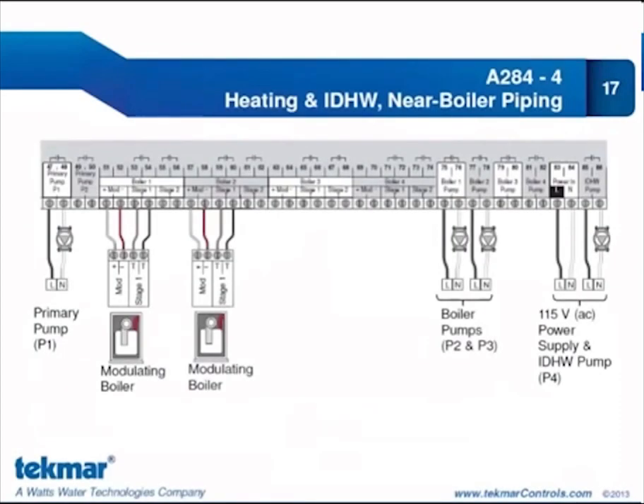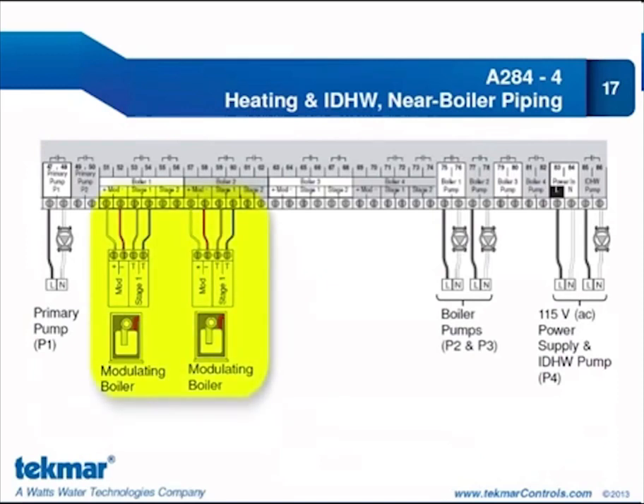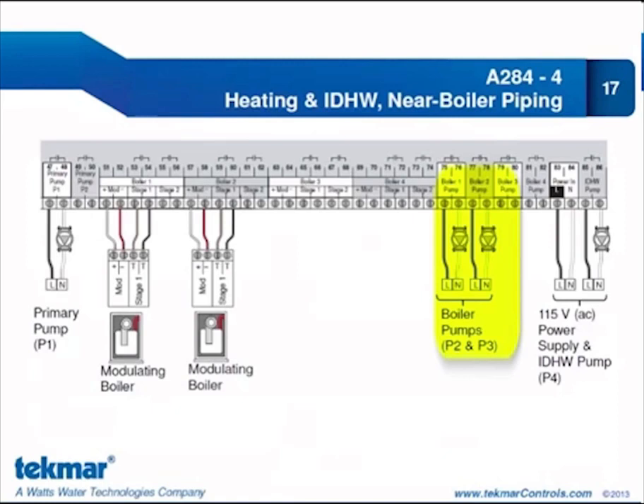Looking at the bottom half of the control for application 4, starting on the left-hand side, we have only one primary pump connection since we are not doing standby operation. Our two modulating boilers both need a modulating signal and a power enable provided by the stage 1 contact closure. Each modulating boiler has a boiler pump switched through a dry contact. We also have our indirect domestic hot water pump and power into the control.